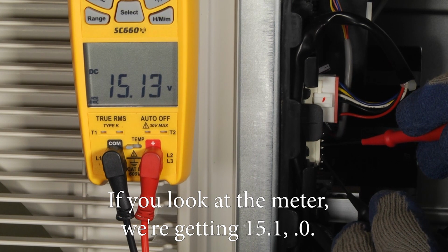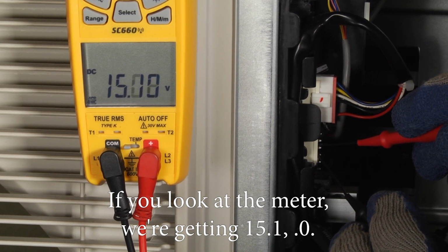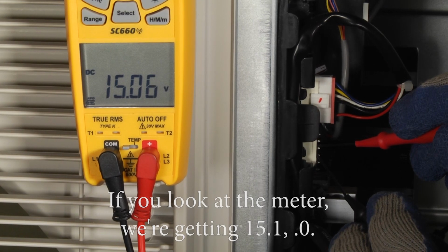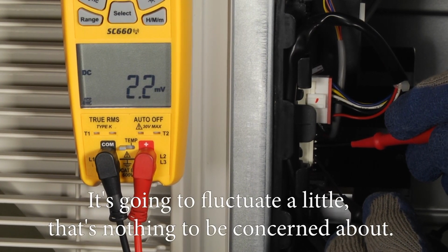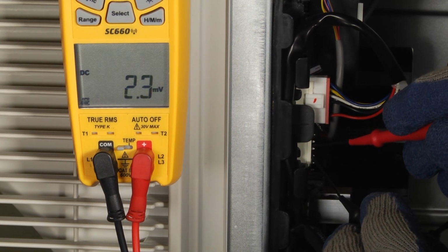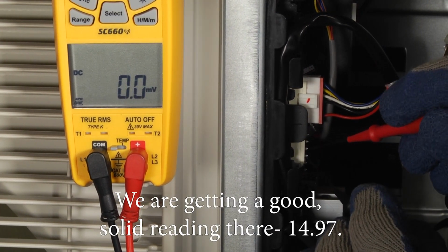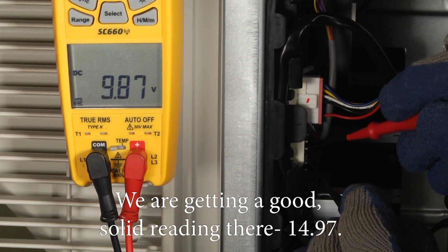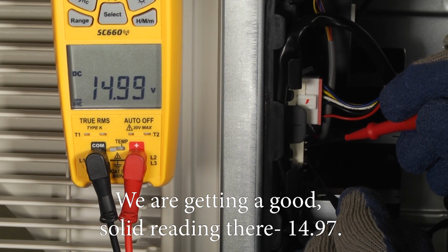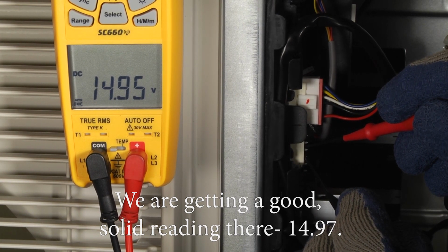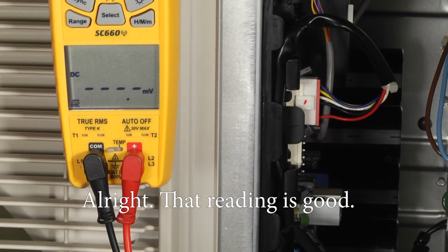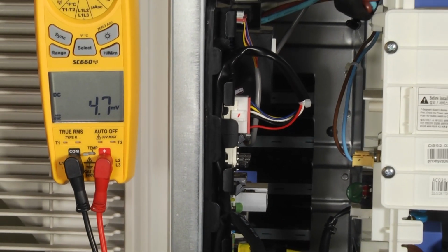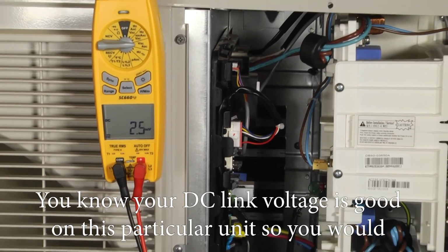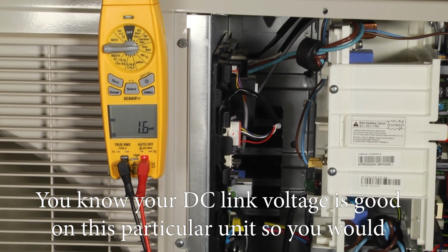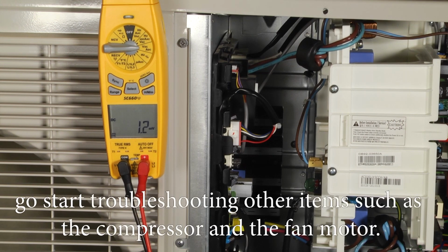If you look at the meter, we're getting 15.1. It's going to fluctuate a little bit. That's nothing to be concerned about. But we are getting a good solid reading there. If I could stay on these pins. 14.97. All right, so that reading is good. You know your DC link voltage is good on this particular unit, so you would go start troubleshooting other items such as the compressor, the fan motor.